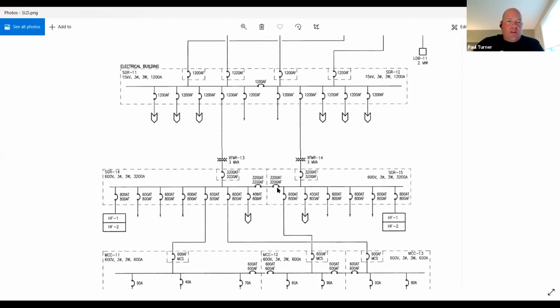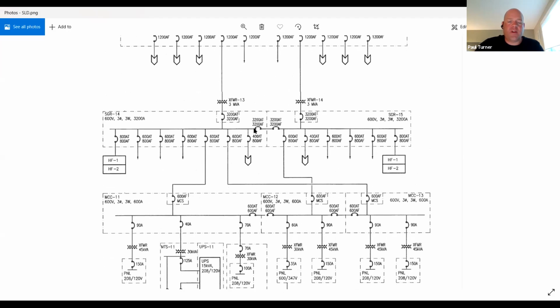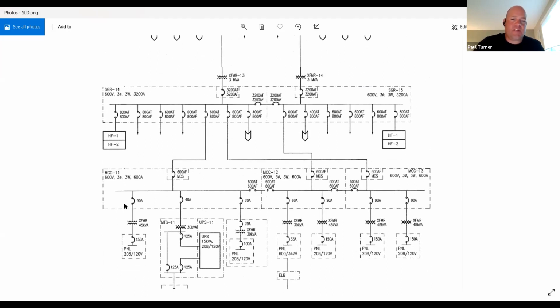Similar to the 15 kV switchgear above, the 600 volt switchgear has a pair of tie breakers as well, and those tie breakers remain open while both the 600 volt bus of 14 and 15 are energized and allowed to soak for a period of time. With everything checking out at that level, you would proceed down to the next level of commissioning, which proceeds to 600 volt MCCs. MCCs are motor control centers, where they provide the 600 volt switching to panel boards and motor control systems. They sometimes can consist of VFDs, variable frequency drives, to control startup and rotation of electrical equipment.